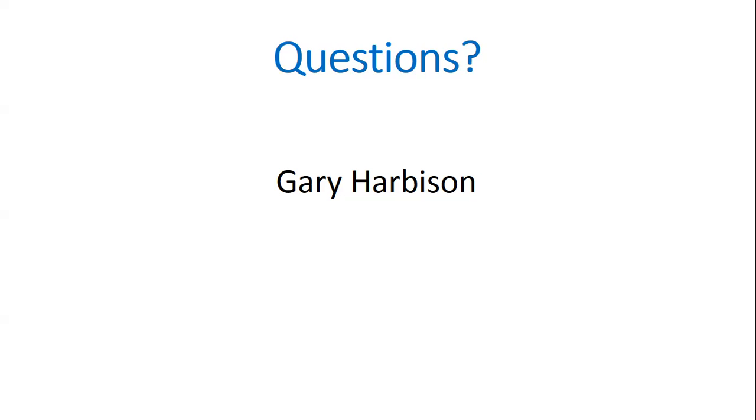I'm Shahid from GSA. I have a question to Josh. You touched upon the boilers with aluminum heat exchangers and issues with the carbon steel pipes. So how bad is it, and what is a good solution to address that? Great question. It's not that it's something that is absolutely insurmountable. It just means that the end solution has to be more complex. And it's simply because the chemistry required to deal with aluminum is not the same chemistry you would do to deal with carbon steel. So which do you treat?